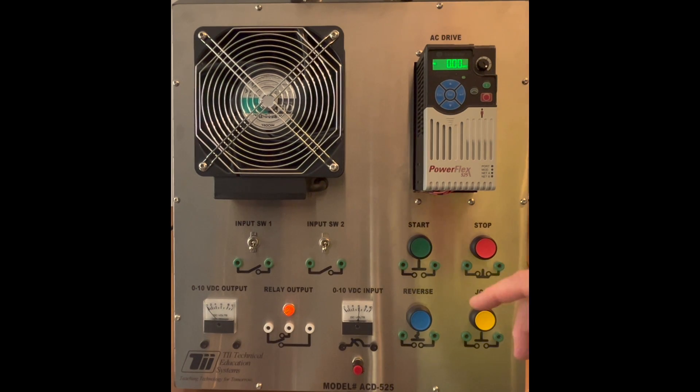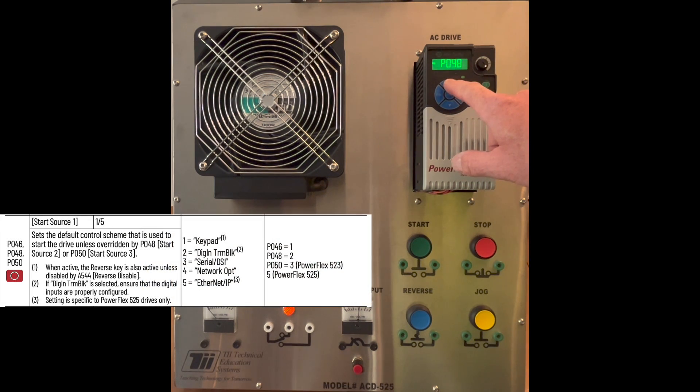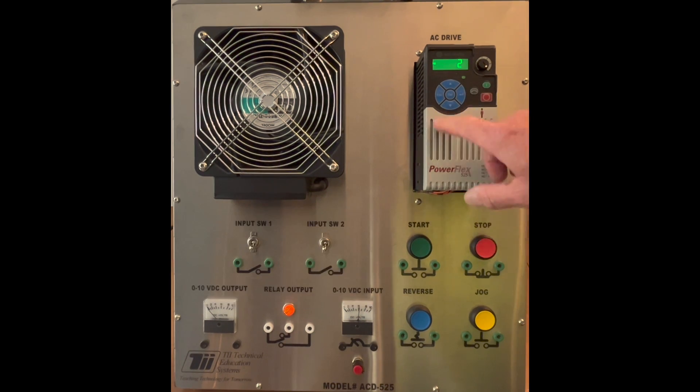So this is how this is programmed. We're going to hit the escape button, and we're going to bring this into P. We're going to bring this up, hit enter, bring this up to 46, and hit enter. We're going to program this to 2, and this will say that we're going to use the terminal blocks as our start button. So we're going to hit enter here.